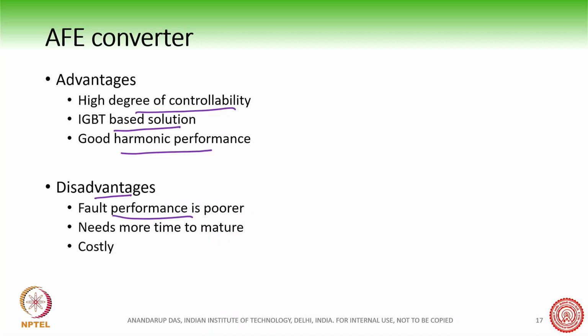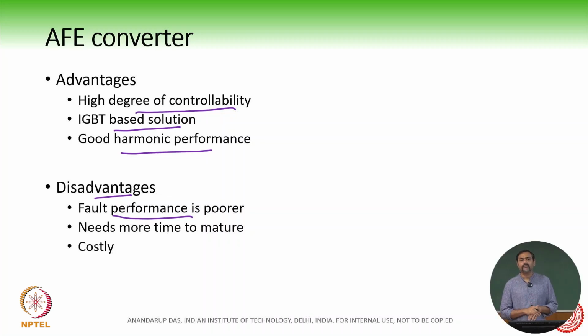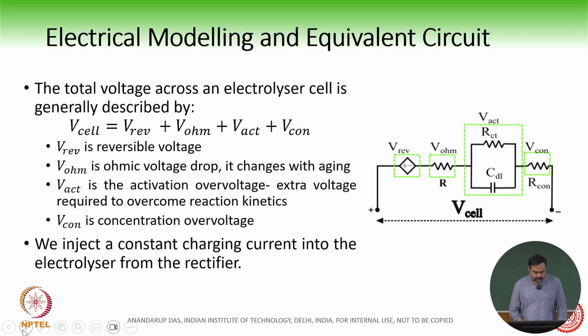The advantage of the thyristor rectifier is more in this respect than IGBT, which needs more time to mature. Although IGBTs are a very mature technology, at this level of current, say 3000 amperes or so, people commercially prefer thyristors till date. As of 2025, people still use thyristors as the main choice, the first choice. So it's a costly one also.